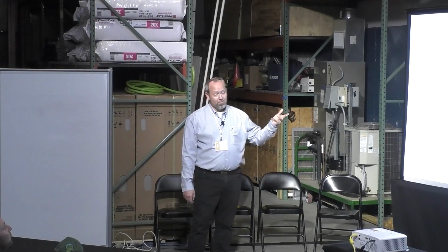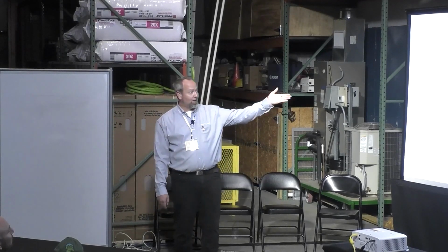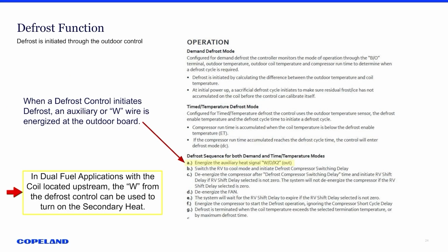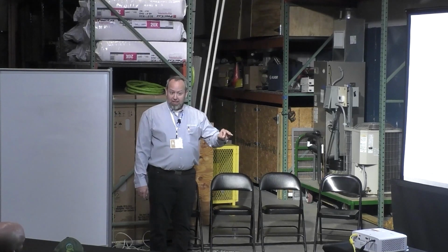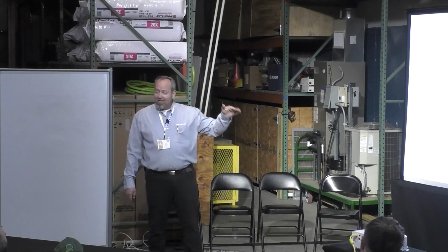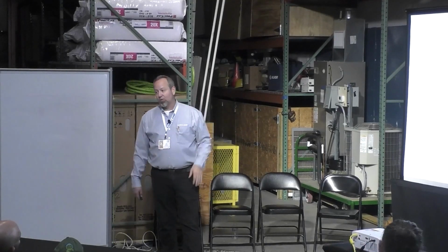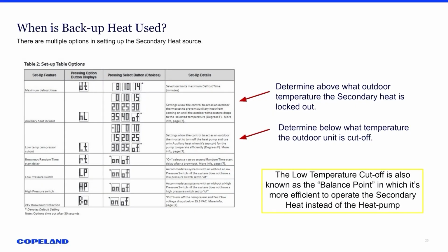And there's two things within our universal board, and most boards, or at least some boards, you should be able to do this. One, auxiliary heat lockout or dual fuel lockout, where you can actually set in the control that the second stage or the dual fuel will not come on until it gets down to a certain temperature, and you can set that at wherever you want. In ours, you can set it anywhere from 0 up to 40 degrees, or turn that feature off. Low temperature cutoff would be what we would use when we're dealing with a balance point, and that's our next and final section here, that we're going to talk about what that balance point is and how that's set.